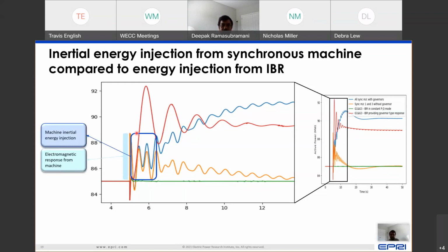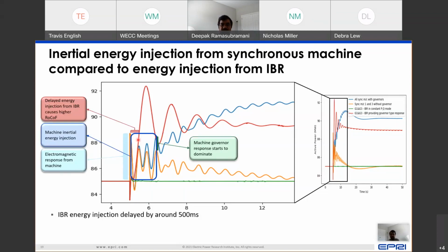So the first spike is pure electromagnetic. The inertial response follows that. You start to see where the governor response becomes more dominant than the inertial response. And in this time duration, definitely yes, the inverter-based resource is more delayed in injecting its power. Here it's 500 milliseconds delayed because it's ensuring that it's calculating the frequency correctly. And it can cause an initial higher rate of change of frequency.